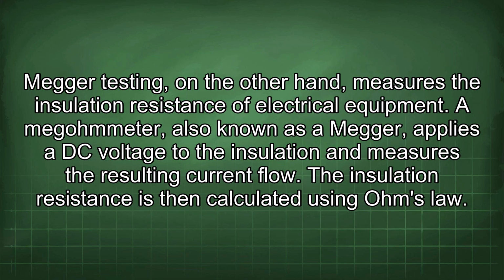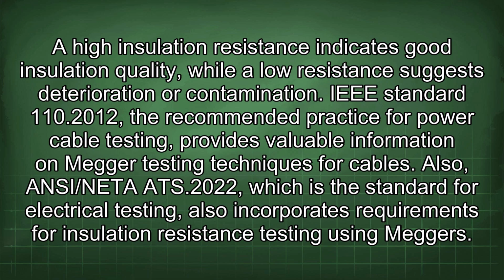Megger testing, on the other hand, measures the insulation resistance of electrical equipment. A megohmmeter, also known as a Megger, applies a DC voltage to the insulation and measures the resulting current flow. The insulation resistance is then calculated using Ohm's law. A high insulation resistance indicates good insulation quality, while a low resistance suggests deterioration or contamination.